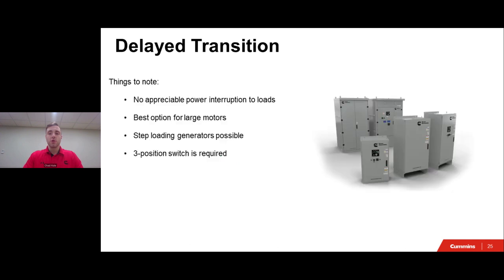So some things to note about this transition are that due to the rapid transfer time, there is no appreciable power interruption to your loads, provided that the system is properly adjusted. Unlike in-phase transfer, this type of transfer is a great option for those large motor loads and allows for the step loading of generator sets. However, please keep in mind that you will need to have that three position transfer switch to accomplish this type of transfer. This is once again due to the need to have that center off position.